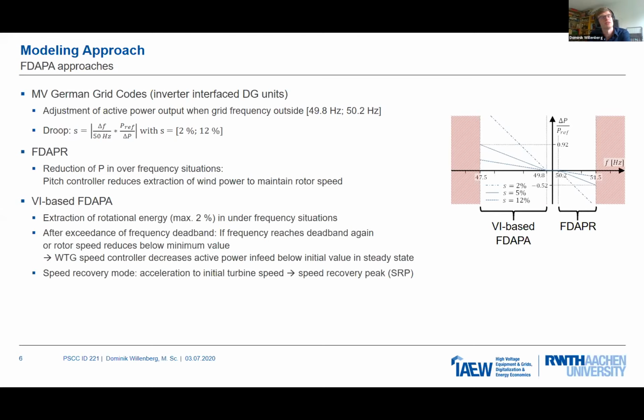Here, after the exceedance of the frequency deadband, so below 49.8 Hz, the active power is increased. This is performed until the frequency reaches the deadband again, or the rotor speed reduces below a minimum value. When these cases are reached, the WTG speed controller decreases the active power even below the initial steady state value, so even below what it was before the under-frequency situation occurred. This is called speed recovery mode and has the aim to accelerate the turbine to its initial speed again. Usually, hand in hand with this comes the speed recovery peak, so a second dip of the frequency.